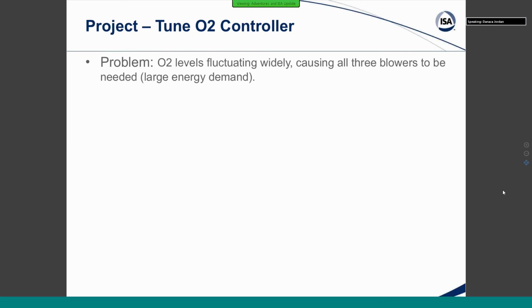So this is an oxygen controller. It's actually also out on our bioreactor. With the aerobic type of bioreactor like we have, you do have to maintain oxygen levels in there within a reasonable range. Otherwise, all of your bugs die. So here, the O2 levels, we were seeing them fluctuate all over the place. It was very, very difficult control, and this was causing our three big air blowers to fluctuate as well.